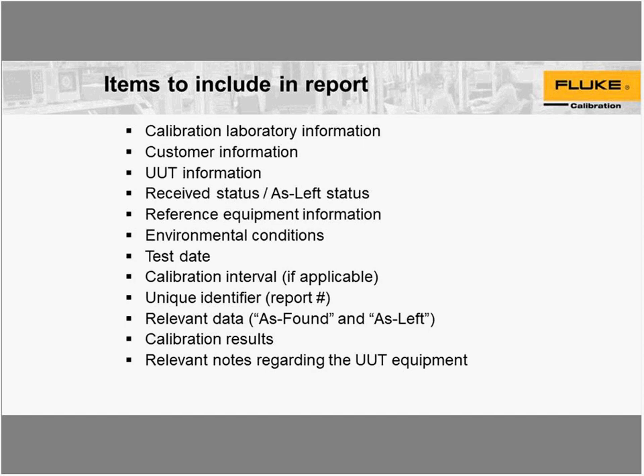Okay. Then last of all, you want to have any relevant notes regarding the UUT or DUT equipment. For example, it passed very well, but the sheath on the cable is starting to crack and may need to have some maintenance done to it. Whatever you feel. You can say that it is still within spec, but it might be having trouble, so pay attention to it. You can do anything you want with relevant notes, as long as they're relevant.